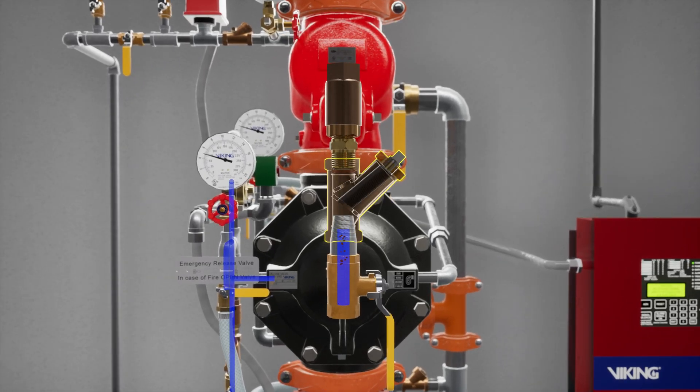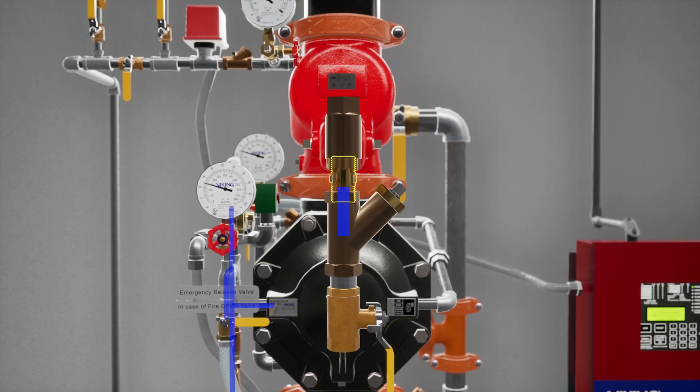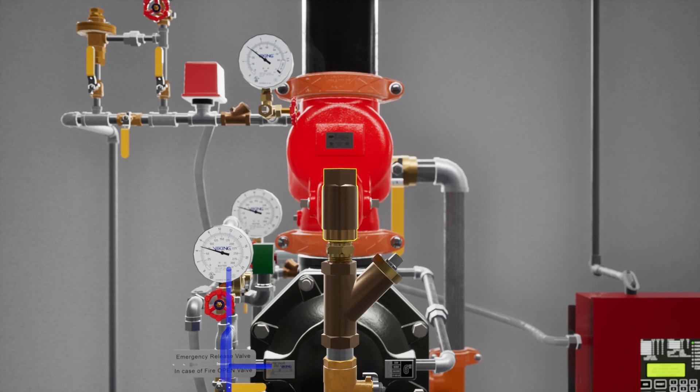The Y strainer keeps debris from entering the restricted orifice. The restricted orifice reduces the rate at which water can enter the prime chamber, ensuring the prime water will drain faster than it can be supplied. The check valve only permits water to enter the priming chamber, allowing prime chamber pressure to be maintained.